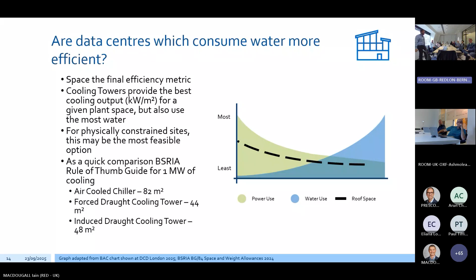As a quick comparison, just using the BSRIA Rule of Thumb Guide: for 1 megawatt of cooling, an air-cooled chiller needs 82 square meters of plant space, whereas a cooling tower needs 44 or 48, depending on the type. So for a given physical roof space, you could in theory get twice the amount of cooling for that same space. It's another efficiency metric that we look at in Global Switch to say, well hold on, I've got a physically constrained building - how much cooling can I actually get out of that roof?